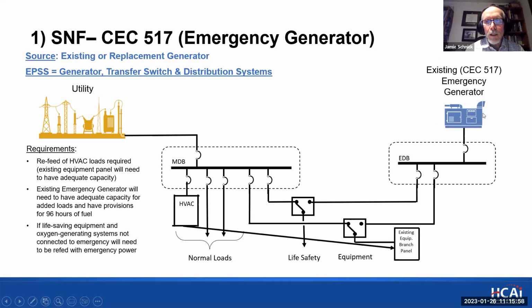And the requirement for 96 hours of fuel would need to be met for this site. Typically, we said those generators would have 6 hours. And ideally, if you have this capacity on your generator, we definitely think this is probably the least impactful way to come into compliance with the code.